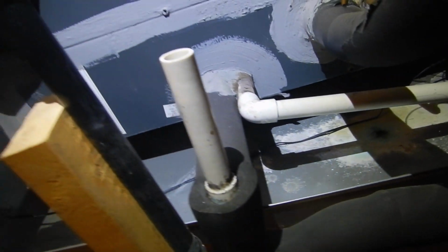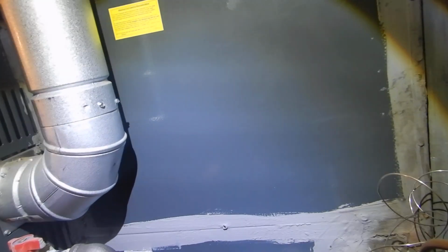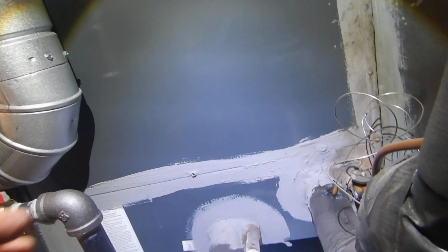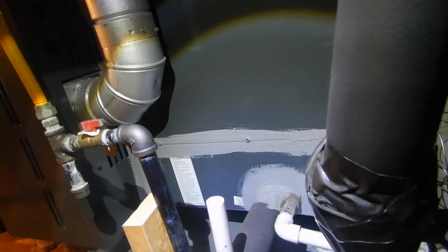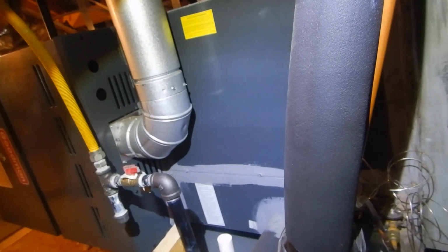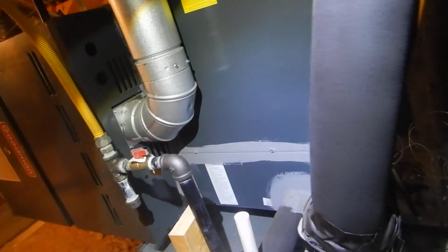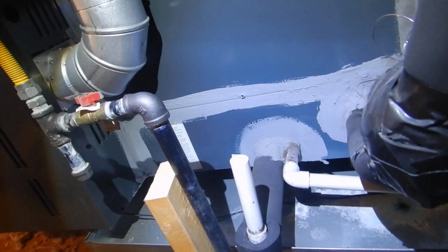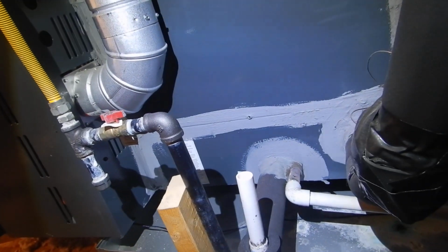Now the trap, by being shallow, okay, and this is running, it's raking the heat out, and it's also creating condensation. That's why your car leaks water when you go into the store for a pack of smokes. You come out, you see a little puddle of water, that's just the air conditioner. Well, this does the same thing. So what happens with the shallow trap is all the air is going across the coils here. And it's raking the heat out, not all of it, and it's raking the moisture. It dehumidifies the house. That's a byproduct of it. And so then when it turns off, all the water drops. When the water drops, it comes down here like it's supposed to.